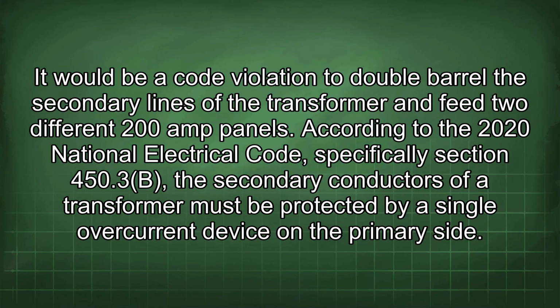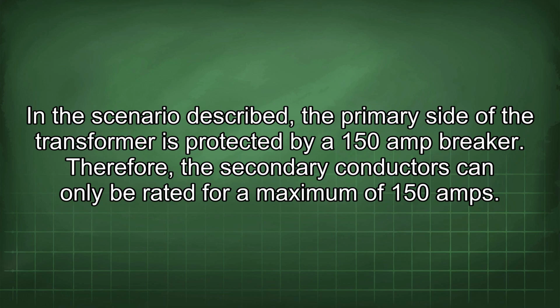It would be a code violation to double-barrel the secondary lines of the transformer and feed two different 200-amp panels. According to the 2020 National Electrical Code, specifically Section 450.3b, the secondary conductors of a transformer must be protected by a single overcurrent device on the primary side. In the scenario described, the primary side of the transformer is protected by a 150-amp breaker. Therefore, the secondary conductors can only be rated for a maximum of 150 amps.